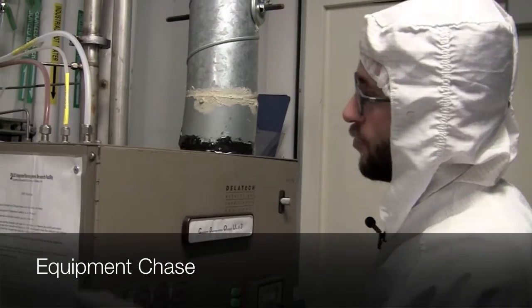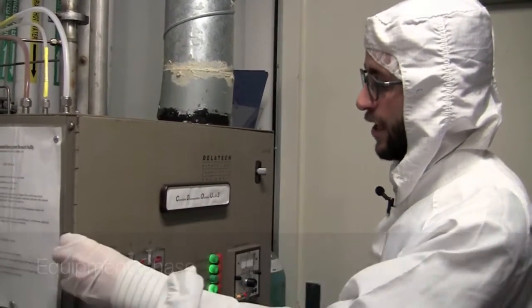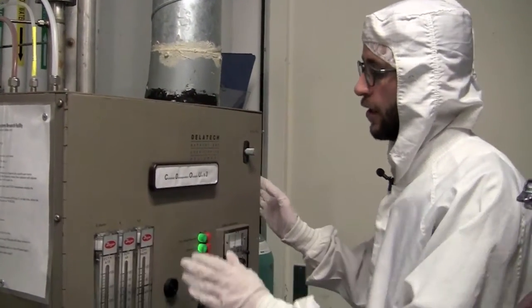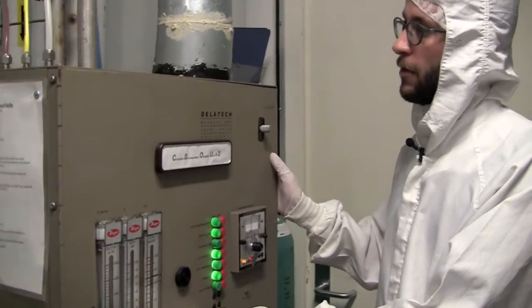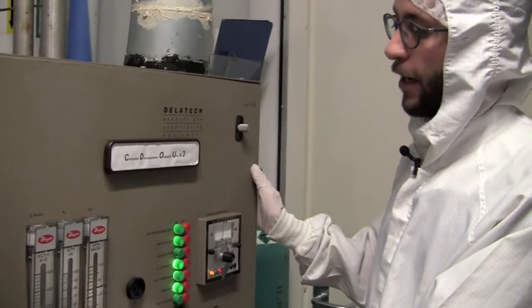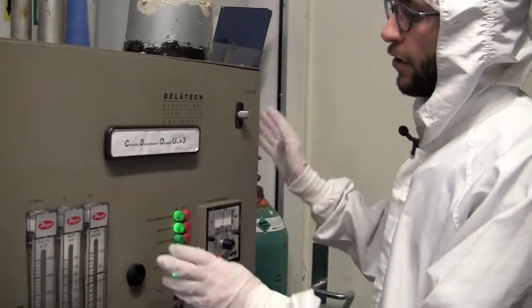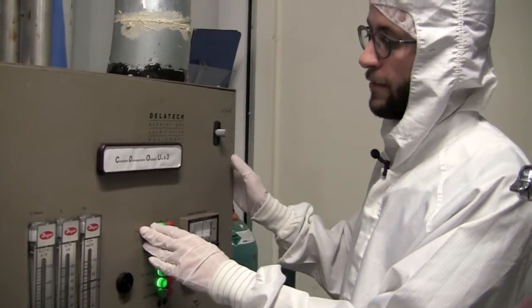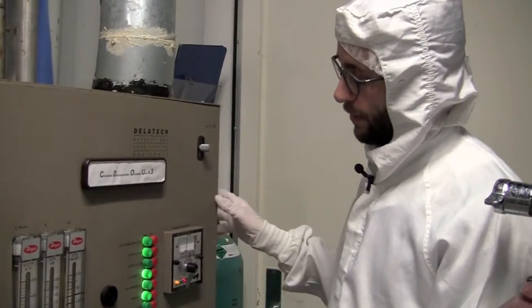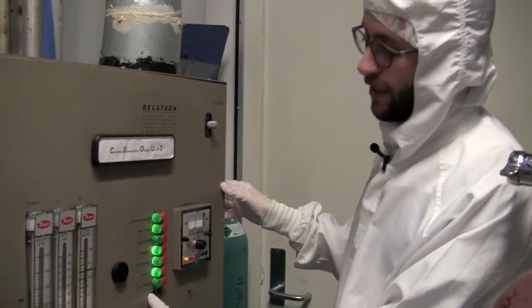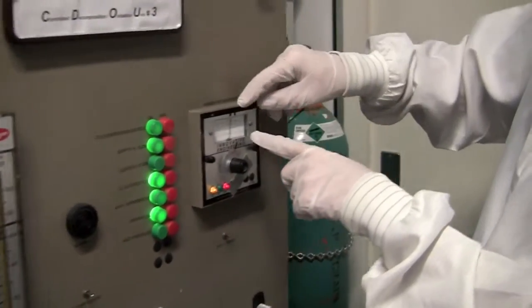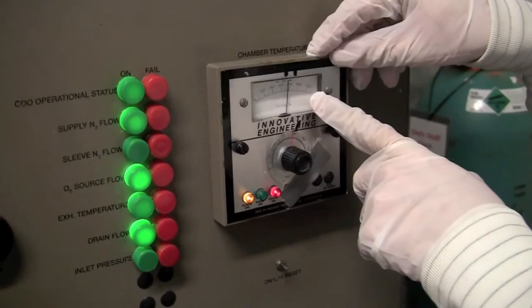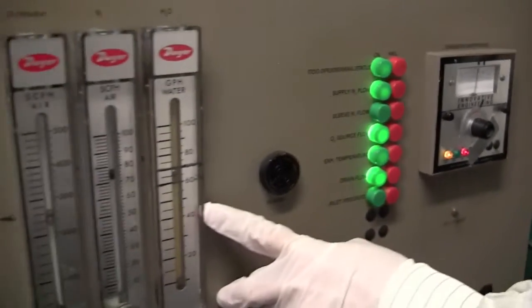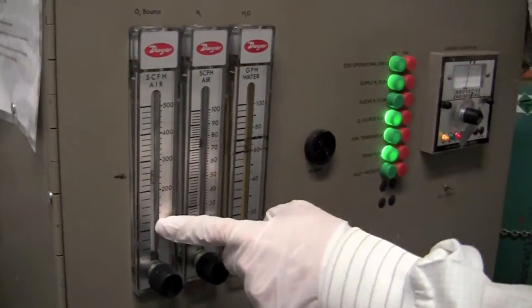The first thing to check in the gas chase is the CDO box. The CDO box is responsible for neutralizing the exhaust gases from the STS, by burning them, which makes them harmless. We have to check that all the lights are green and the temperature is within parameters, as well as the levels of the water, nitrogen and oxygen.